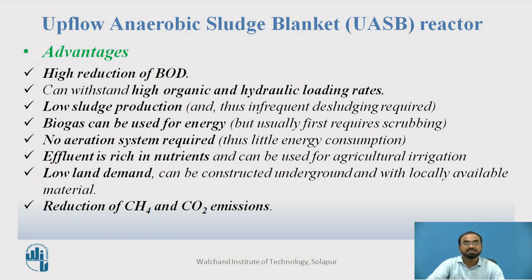Let us see its advantages. It has very high reduction of BOD. It can withstand high organic and hydraulic loading rates. Low sludge production — only 5% — means infrequent desludging is required. The biogas can be used for energy. No aeration system is required, so automatically less energy consumption is needed for running UASB. The effluent is rich in nutrients and can be used for agricultural irrigation. Low land demand as it is typically constructed underground, so the surface area required is very much lesser. It also requires locally available materials for construction, reducing construction costs. There is also reduction of CH4 and CO2 emissions.